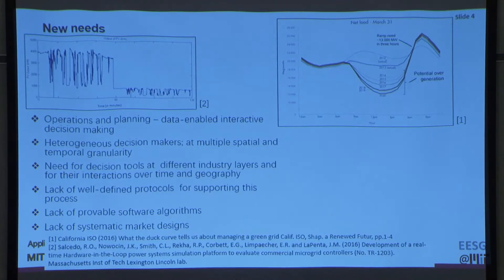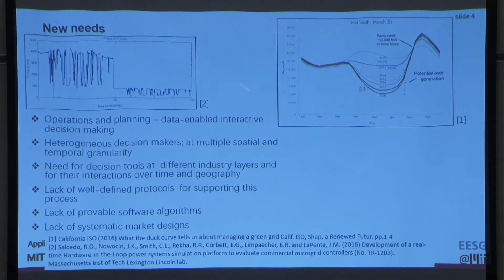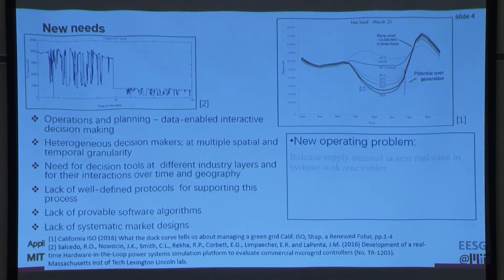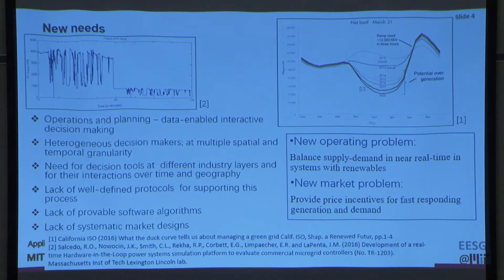There is increased penetration of solar and wind resources, creating a lot of ramping requirements. This figure shows the California ISO duck curve, where the ramp requirement is increasing every year. This is a sample plot of grid-scale solar PV when a cloud passes at noon, showing how fast the fluctuations are. This poses new operating problems — the operator must balance supply and demand in near real time — and also new market problems, as price incentives must be given for fast-responding generation or controllable demand.